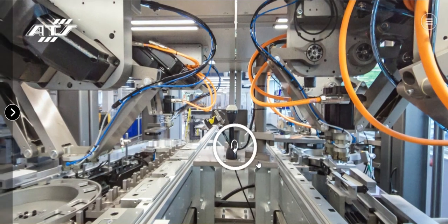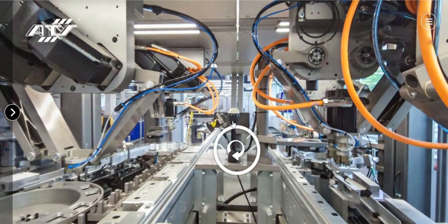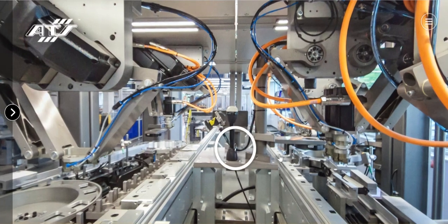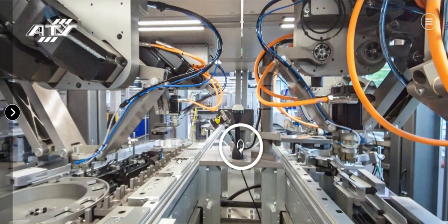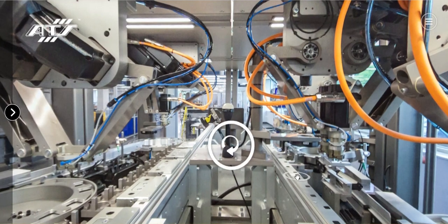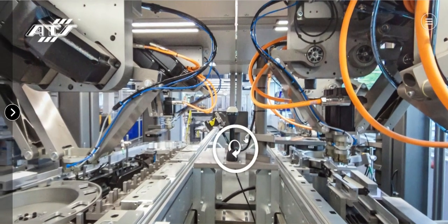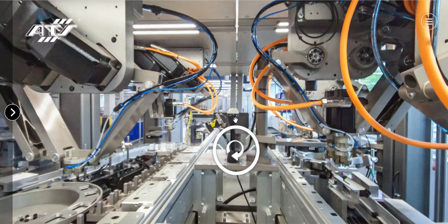If they are not in a position that is safe to restart the machine, the light will be red. What's the correction for that? Well, the correction is basically for a technician to come in and move any pallet that is out of position into a position that permits the station to restart safely.